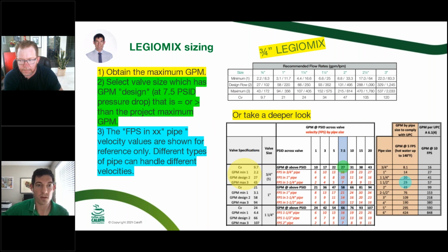Now we go to the green shaded area. We want to see what the pressure drop is across that valve. A lot of engineers shoot for that 7.5. Some will go up to 10, some will go down to 5, but we recommend 7.5. So if we look at the green shaded area there, now I can walk down below that 27. That's our design GPM. Below that, let's say we were using all 3/4 inch pipe. The velocity, the red numbers, is going to be in feet per second.